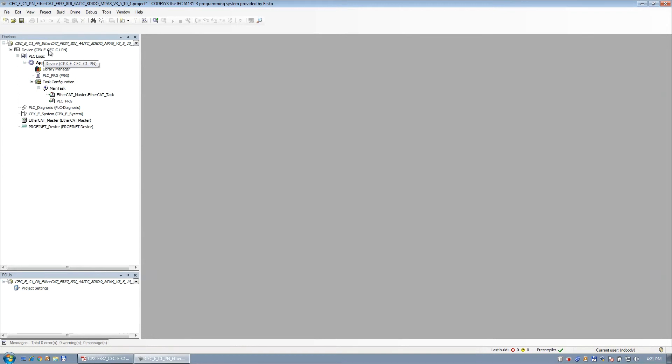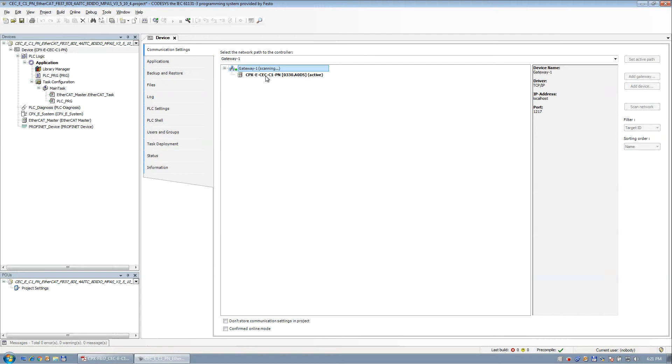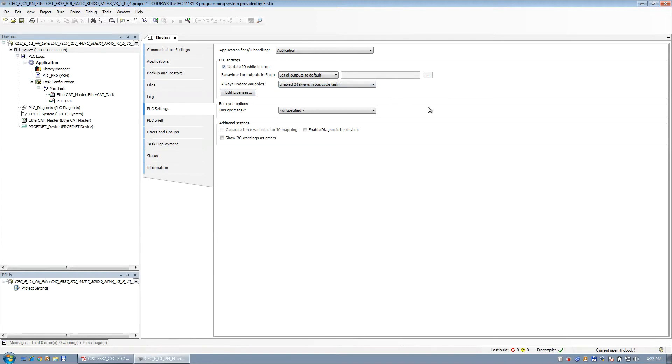So first thing you do, double click on the PLC, and you need to make sure that you can scan the PLC on the network. Okay, so set this as active target, or double click it. I like to come into this setting right here. Click on a couple things right here. This allows the I/O devices to be updated automatically all the time, whether you're in run or stop.